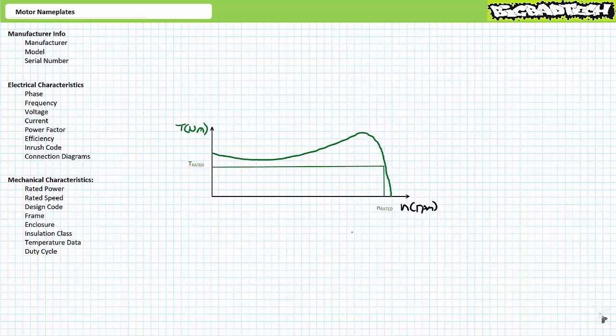Operated at anything other than the rated condition, in excess or below the specified point, a majority of the entries on a motor nameplate are subject to change. For example, if an induction motor is excessively overloaded, we might expect its speed to decrease, current to increase, and efficiency to decrease, among other effects. Data at other than the rated condition is customarily not found in the motor nameplate, but rather it can be found in the motor's associated data sheet. A motor's complete data sheet will specify properties for a range of operating conditions, customarily on one or more charts. We'll examine motor data sheets and properties at other than the rated condition in later lectures.